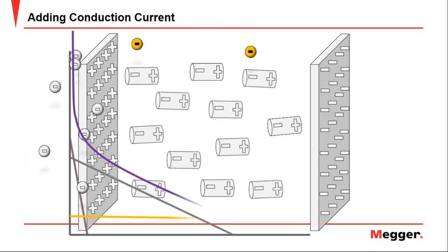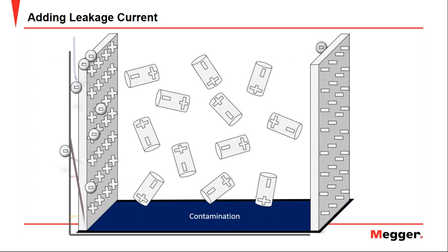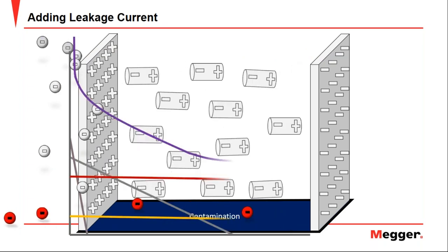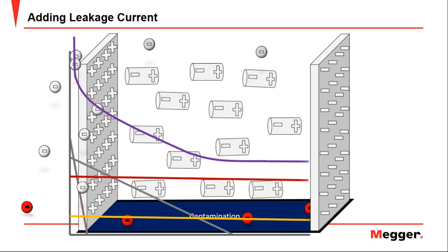Now, let's add the conduction current. This current is constant, but very small. So it will add a very small value to the total, as we can see in the animation. And finally, we can add the last current, the leakage current, which, as we know, is the current that will circulate through the contamination and/or the degraded insulation. And because it is constant over time, at the end, we will have a behavior like the one shown in the presentation. Therefore, if we wait long enough, only the leakage current will be present in the measurement.